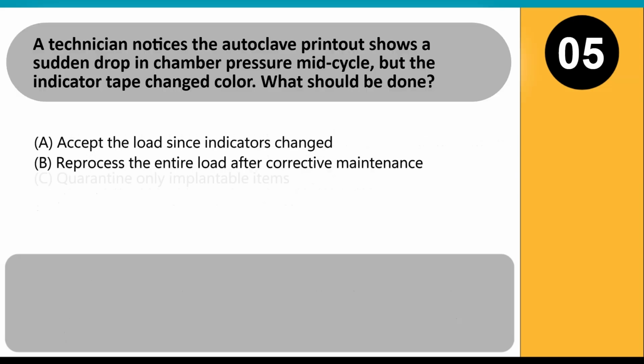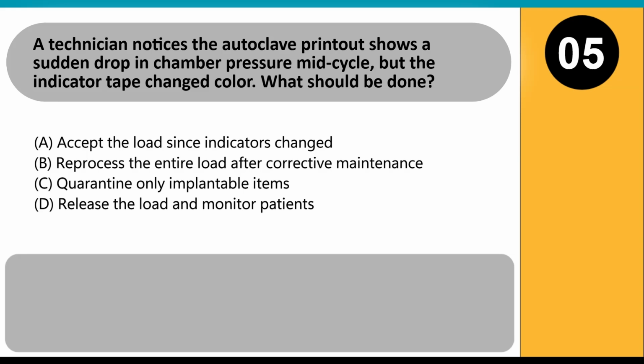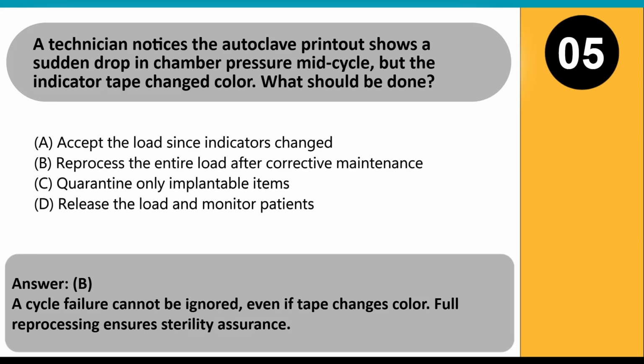A technician notices the autoclave printout shows a sudden drop in chamber pressure mid-cycle, but the indicator tape changed color. What should be done? A. Accept the load since indicators changed. B. Reprocess the entire load after corrective maintenance. C. Quarantine only implantable items. D. Release the load and monitor patients. Answer: B. A cycle failure cannot be ignored, even if tape changes color. Full reprocessing ensures sterility assurance.